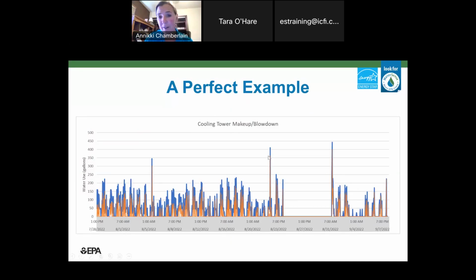The blue here is the makeup. We've got our water use in gallons over here and our time. The blue is the makeup, the orange is the blowdown, so they're pretty in sync. But what we see is a whole week where we had no makeup and no blowdown. On the 24th they did a service visit, and they didn't come back until the 31st. That whole time that tower didn't run, but they thought it was running because the energy management system was saying that the pump was running.